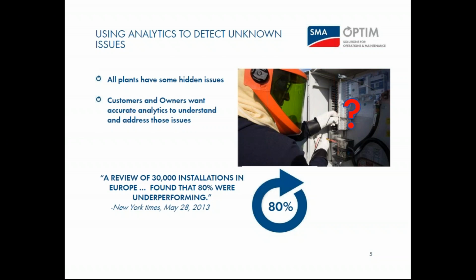At SMA, we see a lot of issues that show up as an alarm or error in the inverter, and that doesn't matter where it happens in the plant. A lot of that information tends to flow through the inverter, so that's where it's getting picked up a lot. But some of the more common issues we're seeing come from modules and cabling, and those can be responsible for over 60% of the issues at a plant.